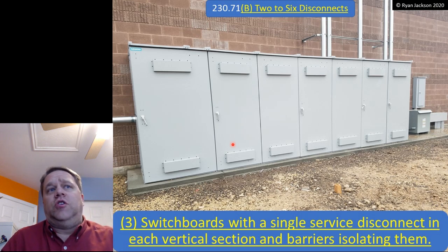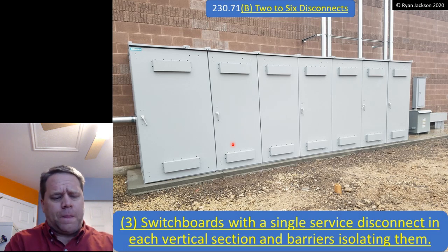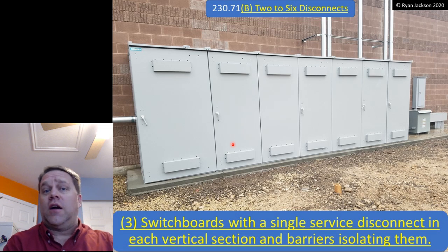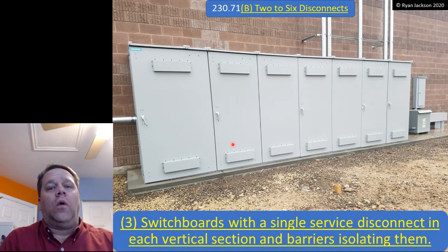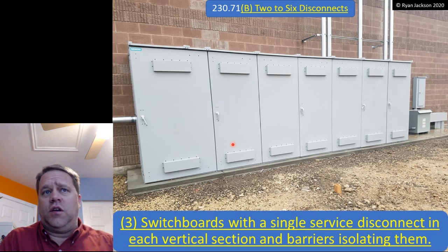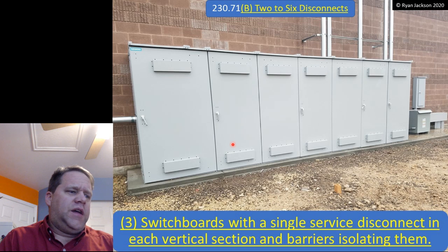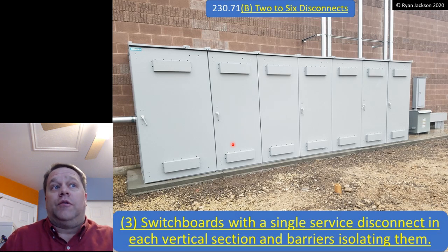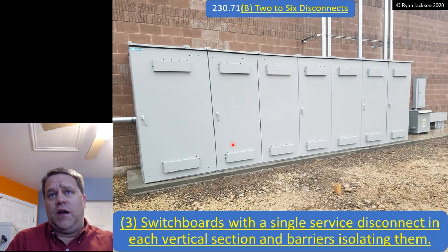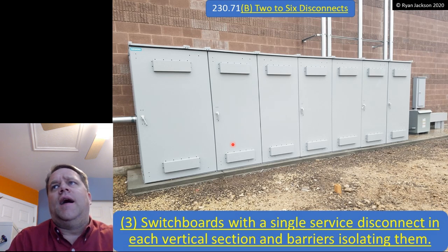There's only 2 times you should be working energized. One is if you're measuring for voltage or lack of voltage because you're troubleshooting, you know, you're measuring current, something that has to be done while it's on. Or number 2, if shutting it off actually creates a greater hazard than working it energized. You can't shut off the fire alarm panel for a high-rise building. You know what I mean? If something went wrong, we could have thousands of dead people. So there are instances when you can work energized, but very few and far between. So I want to make sure that we're clear on that.